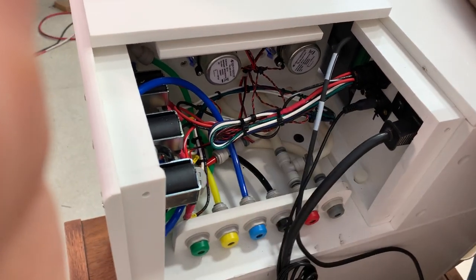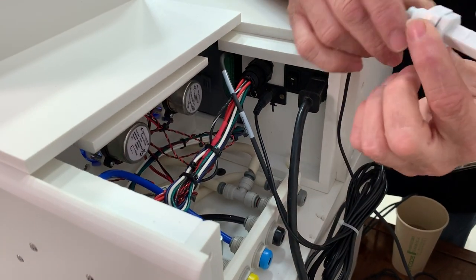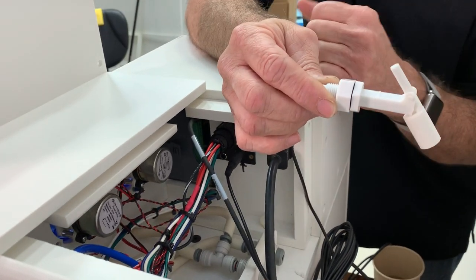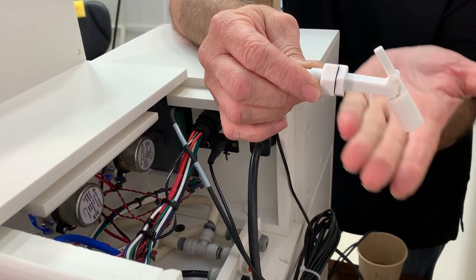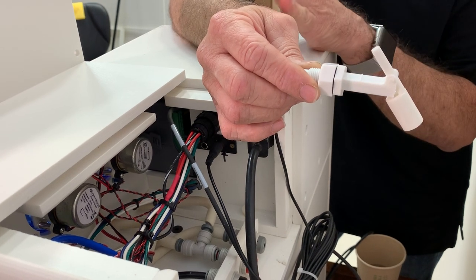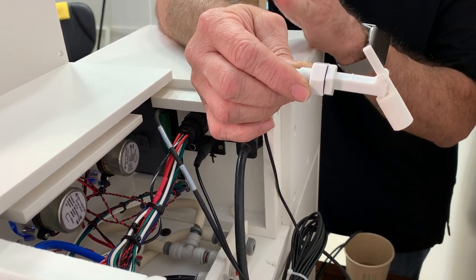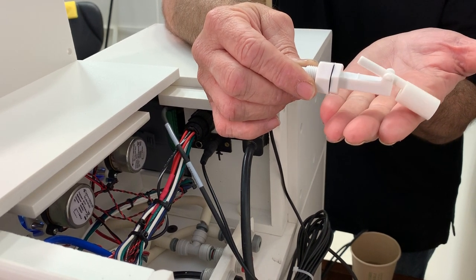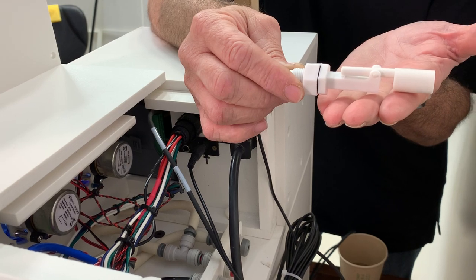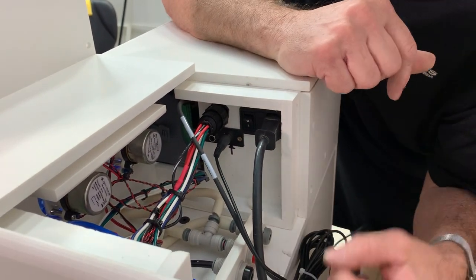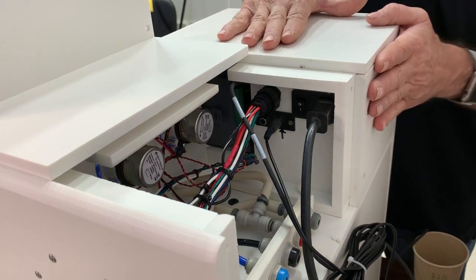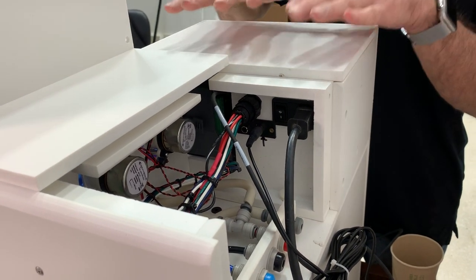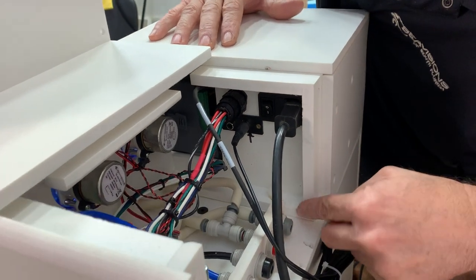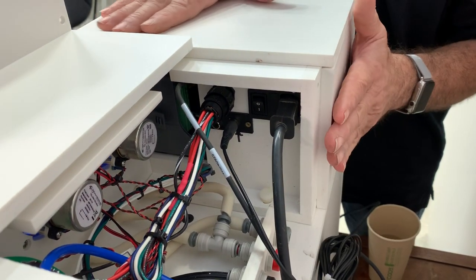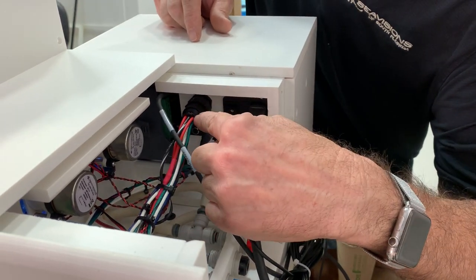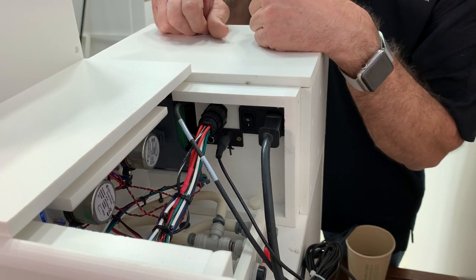There is a port here for your float switch. This float switch will go in your sump, and it is kept at the level that you want to maintain in your sump. When the float switch is hanging, this machine will stop the dialysis process, and it'll only add DI water to your tank. Once the DI water fills up your sump and it goes to here, it will start the dialysis process. If you ever had to send your computer back for service, the whole machine can stay plugged in. You take out one screw here and this whole head unit will slide out. You disconnect this cannon plug, and you can send this unit in for service.